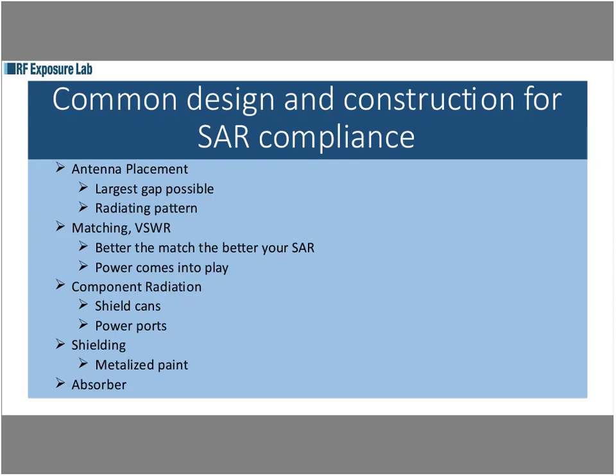Common design and construction. These are just some general things that can help in design work. Your antenna placement, obviously, the largest gap possible will give you the best ability to pass the SAR requirements. The closer the antenna is to the body, the higher your SAR value is going to be. Your radiating pattern, if you can push most of your energy away from the side that's normally going to be next to a body, then you can avoid getting as much energy going into the body and get more energy going away from the body. It's still kind of an issue even with that, in that you've still got a lot of current flow that's close, but if you can push it off to one direction, it does make it a little bit easier.